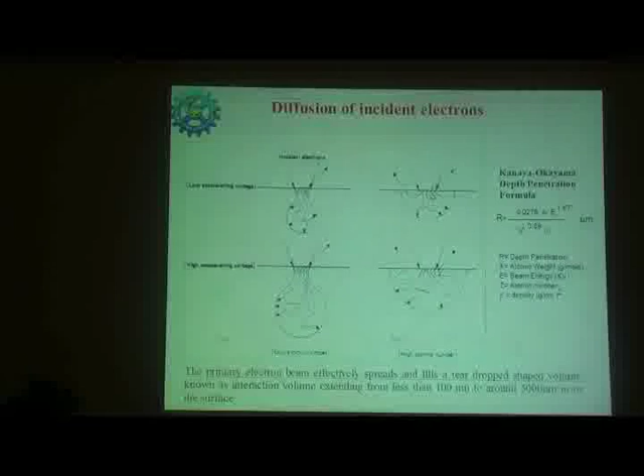But when you take a high atomic number element, suppose I am using something like tungsten or bismuth, which has a high atomic number, the interaction volume is different. It is more hemispherical, and the interaction volume increases with increasing accelerating voltage. There is a formula: the depth of penetration is inversely proportional to atomic number and density, and depends on the accelerating voltage and the atomic weight of the element.